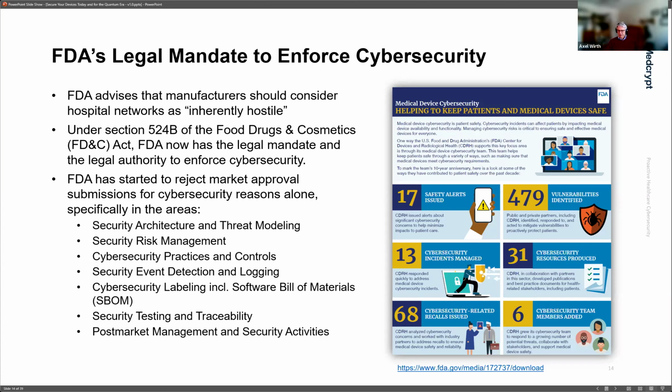And specifically, FDA looks at areas around security architecture and threat modeling, overall your risk management process, your cybersecurity practices and controls you implement, your ability to detect security events and log the events in fielded devices, overall your cybersecurity labeling and documentation, including a software bill of materials, and then security testing and traceability.